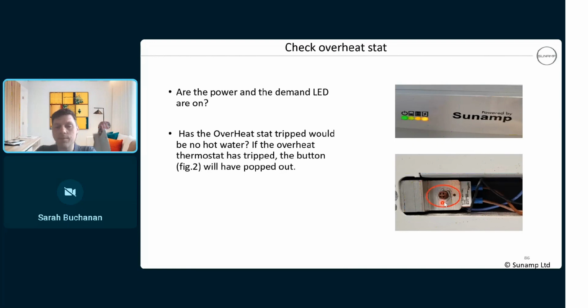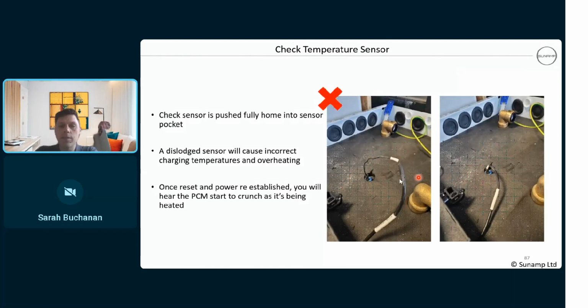So overheat stat tripped, check the button, push it back in. Initially, you will hear something that sounds like you're walking in fresh snow. That's the PCM starting to absorb the heat. Check the sensor, where it's located. This is quite important on the commissioning, because when you're mucking about with the pipes and putting insulation in and out, with different sparkies and plumbers coming and going, just make sure it's pushed fully home there. Because if that's pulled out even a couple of millimeters, that can cause intermittent overheating. If it's pulled out by that much, yeah, it's going to trip out. I've had jobs where that's been pulled out completely and it's not inserted at all.